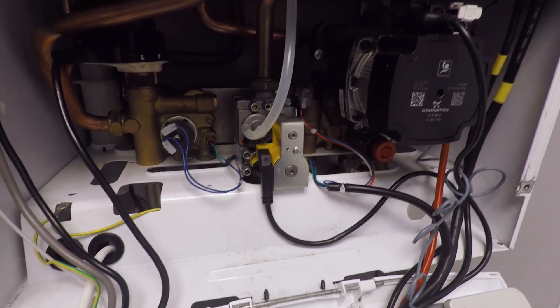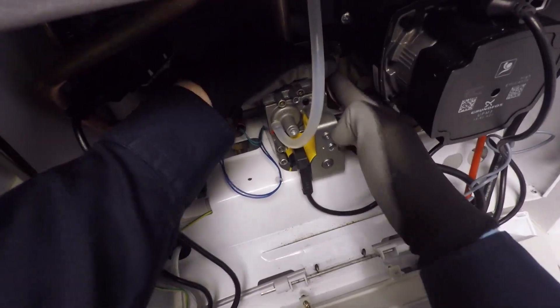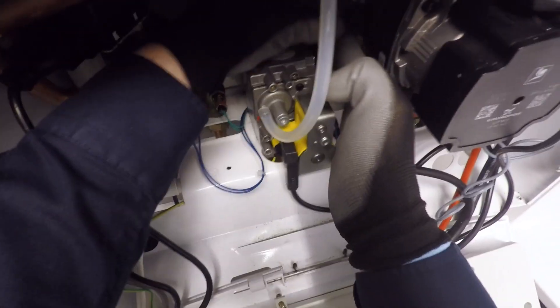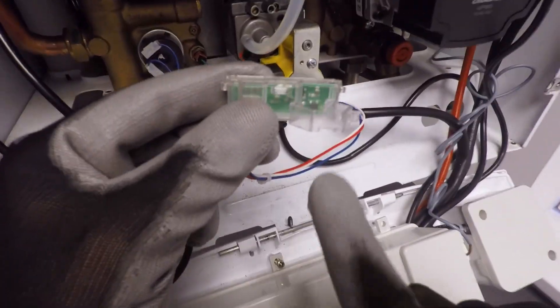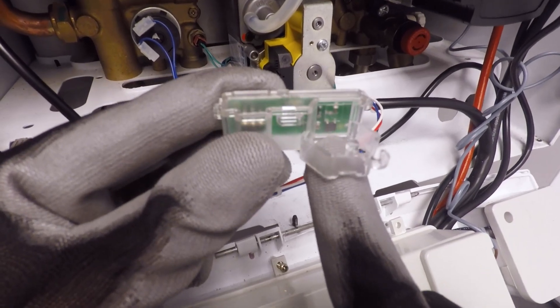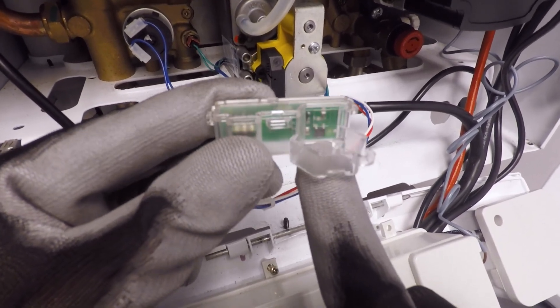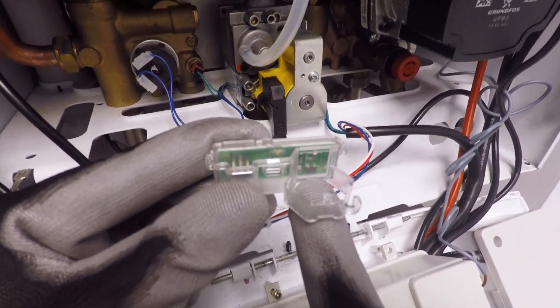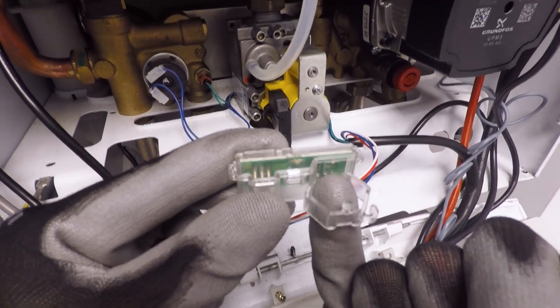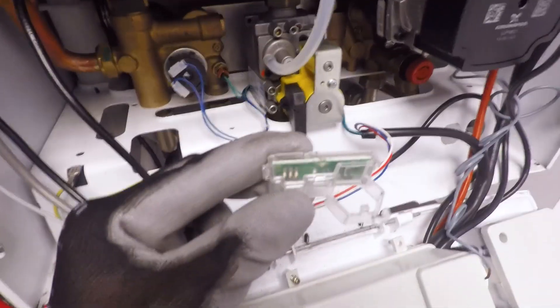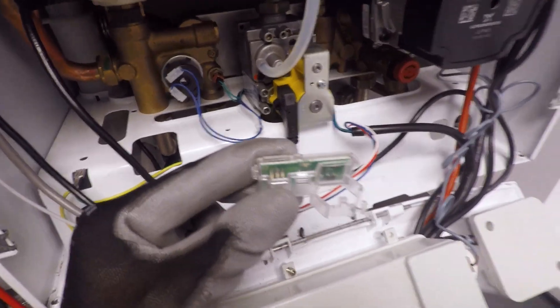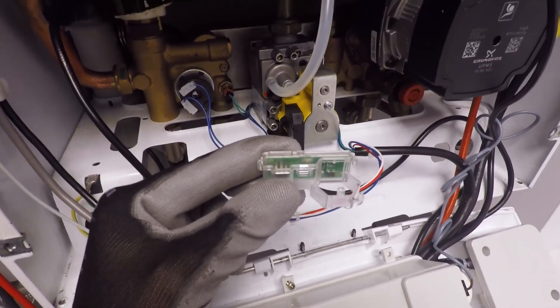So I've got to be quite honest, Anthony, the easiest way of checking the Hall Effect sensor on a Duotec or a Platinum is quite simply with a magnet. So if we look there, hopefully you'll be able to see that little black square, that's your Hall Effect there. As soon as you place a magnet next to that, your red light should come on on your Hall Effect sensor. The boiler recognizes the demand and it will fire up.